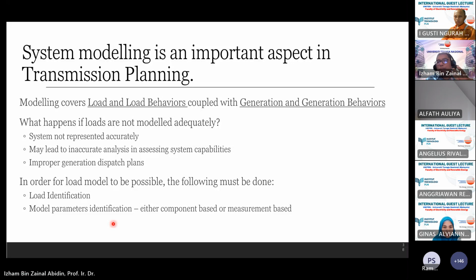However, there are situations where you need to upgrade that static load flow to dynamic simulation, where your models are based on time and you want to see how the generator behaves. You want to see how the rotor speed goes up and down as you have changes in the load. That is usually done by the utility to make sure that the system is stable. Just doing static load flow is not enough. Usually you need to do more by doing dynamic simulation as well.